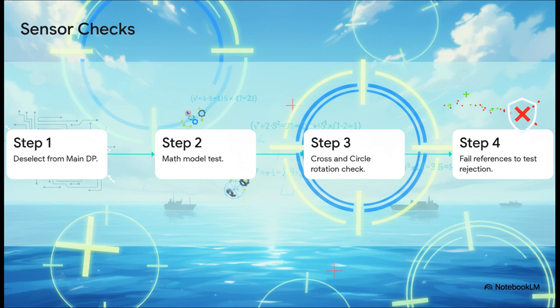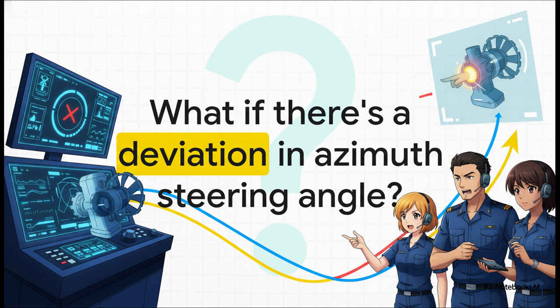Whenever I'm conducting a briefing for operators on sensor failures, I always pose this scenario. What actually happens if there's a deviation between your DP command and the physical azimuth steering angle? Well, the independent closed-loop protection should immediately trigger a prediction error and shut down the drive to stop a drive-off. We actually design strict training scenarios specifically to test this exact failure response.